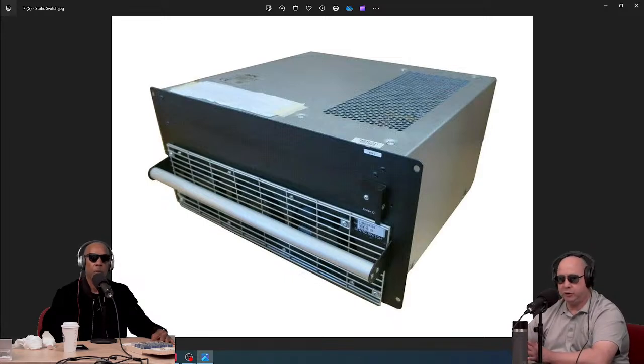Okay, everything in order to perform maintenance. Are you doing any work inside of it? Actually, we do. There's a couple boards, there's relays in there that we'll try to fix, and the power supply card we'll fix. There's a data card, and of course three cooling fans in the front there that we'll replace as necessary. But this gets the same treatment as everything else. We open it up, we blow it out, we wipe everything down, we look for anything that's out of place, check for loose hardware. The same thing that we do for every other modular piece that we work on.